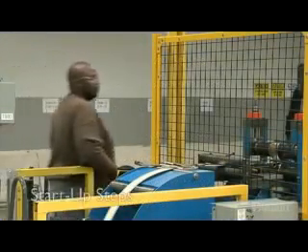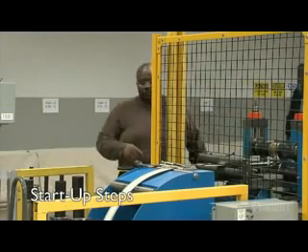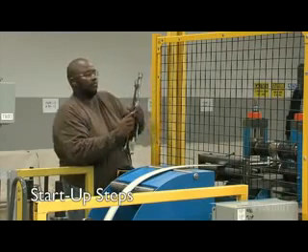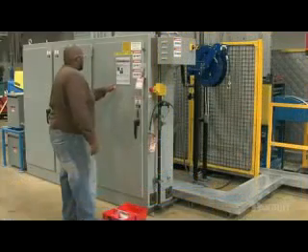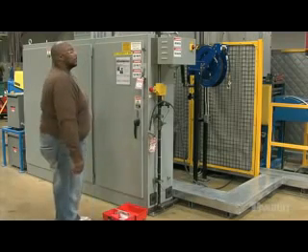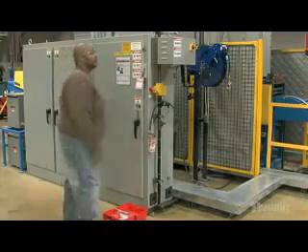Startup is every bit as important as shutdown. When the work is completed, follow procedures for restoring the equipment to running conditions. First, make sure you remove all tools, reconnect any lines, and put machine guards back in place. Before you remove the lock and tag and re-energize the equipment, announce that the equipment is being turned on again and confirm that all employees are safely positioned.